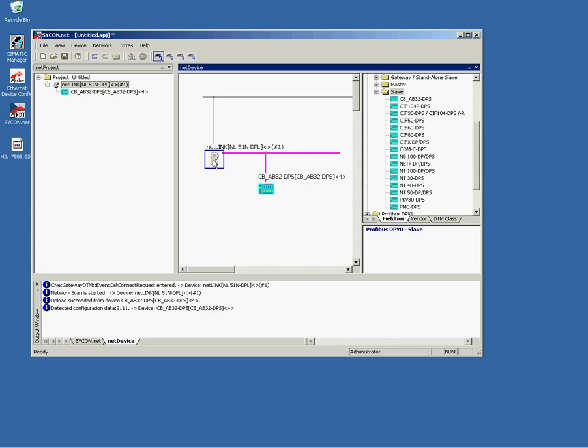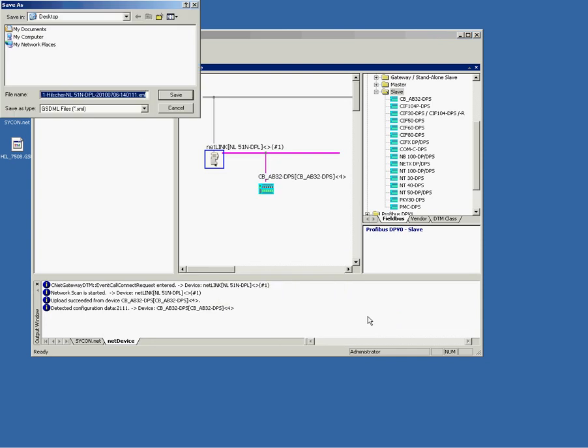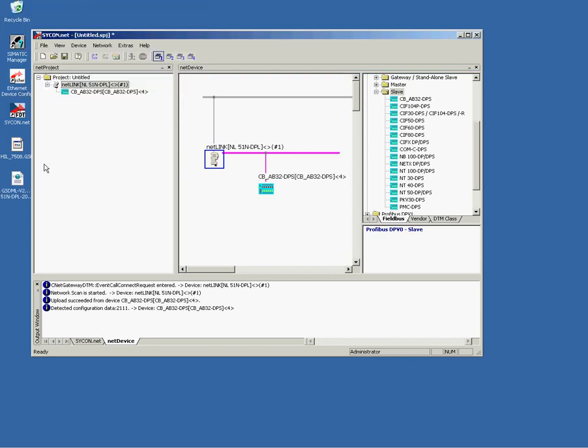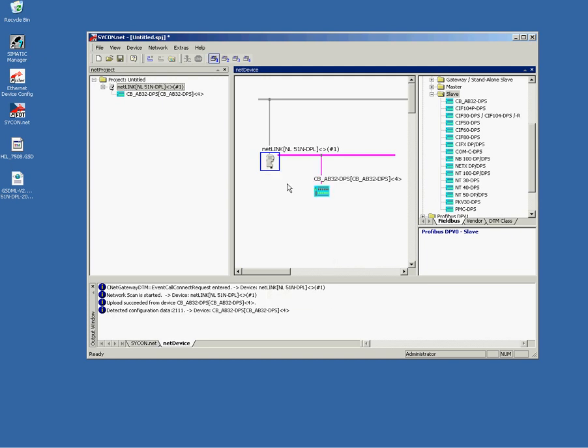The next thing that we are going to do is exporting the GSDML file for the Profinet I.O. controller by right-clicking that link and choosing Additional Functions, Export GSDML file. I set the location to the desktop. See here the file. This file we will import in Step7 later on.